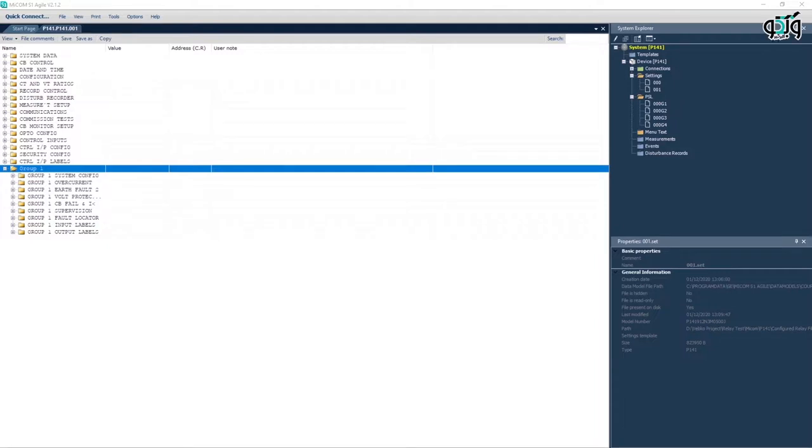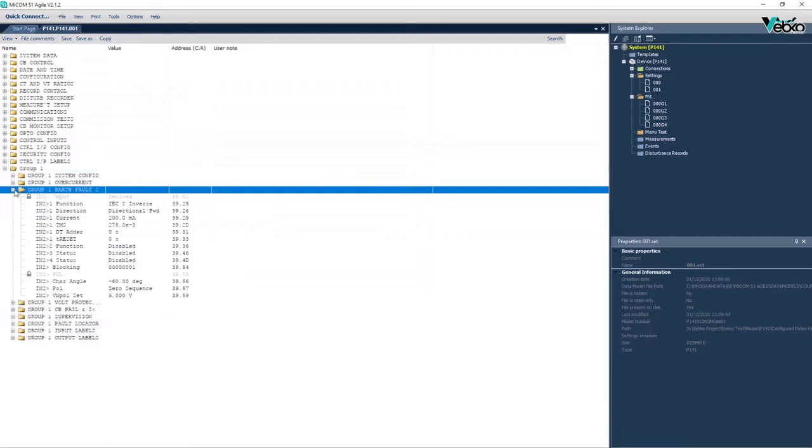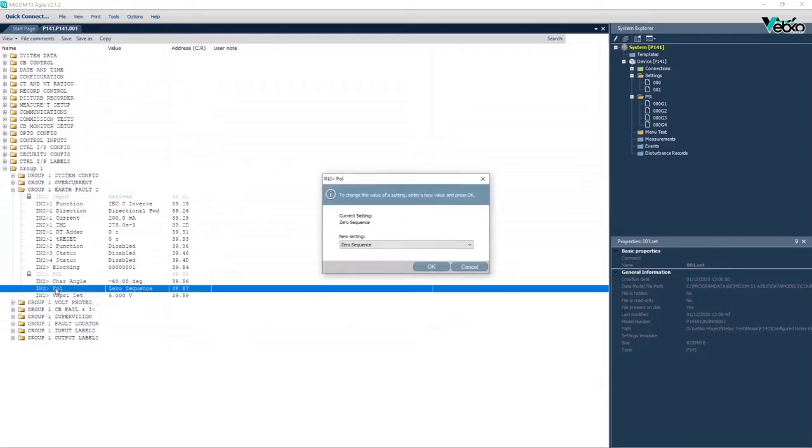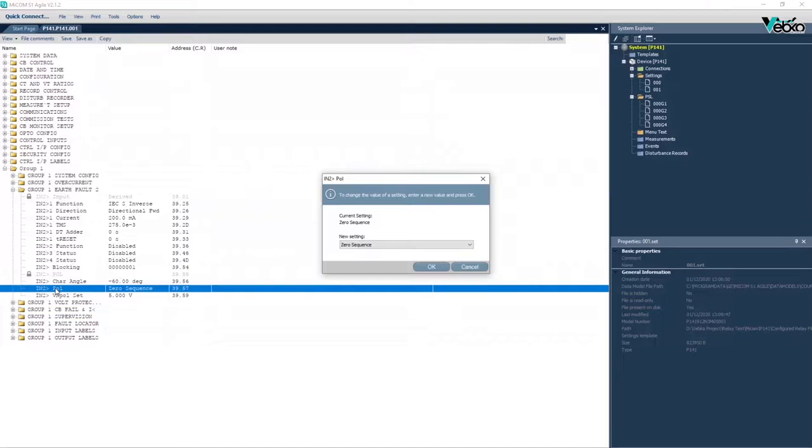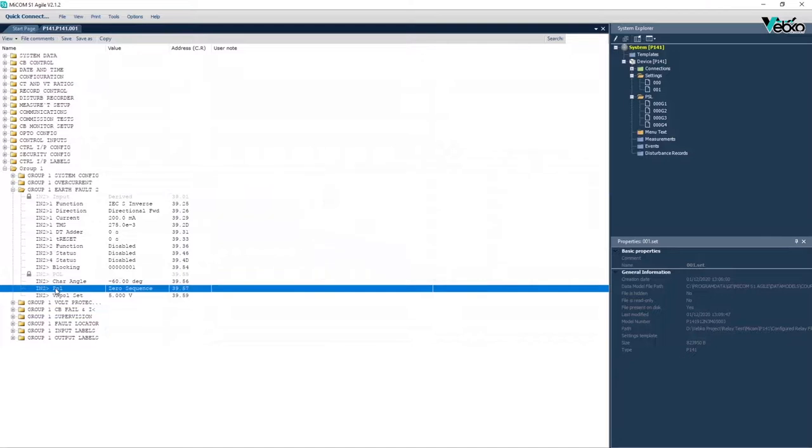For earth fault standard protections, there are two options available for polarization including zero sequence or residual voltage and negative sequence. Here zero sequence is used. Since at the creation time of earth fault, residual voltage is created, it is possible to use this element to polarize directional elements. This process is called zero sequence polarization, residual voltage polarization, or neutral displacement voltage polarization.